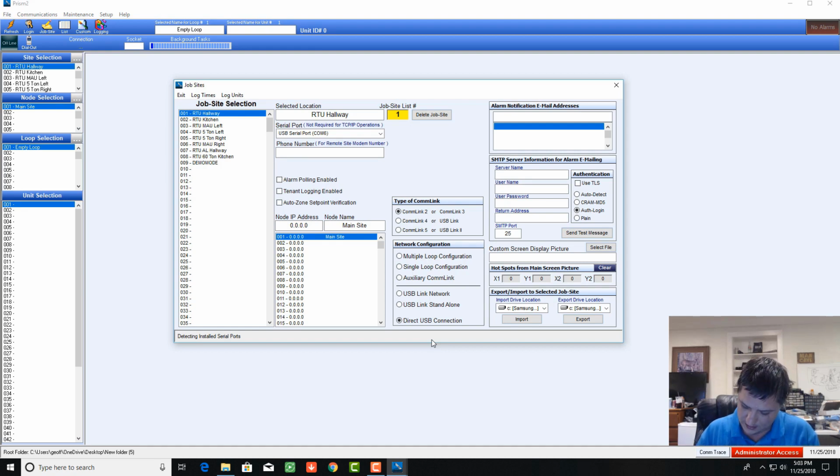Well, why did I buy this? This is the breakout board, so I can take thermostat wire, hook up to the VCMX module on the unit, and I have communications. Why did you do that, Jeff? Why not just go buy a COMlink 2, COMlink 3, 4, 5, whatever USB link? Because they're $475. Why? We will never know. They do the same thing that this does. It's just a communication COM port. So screw that. It's a ripoff and a scam.